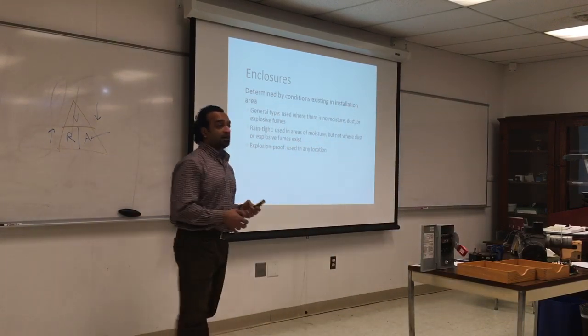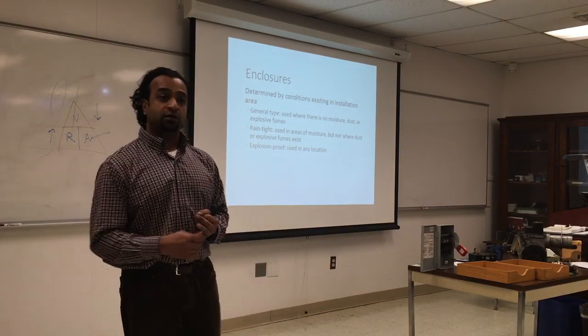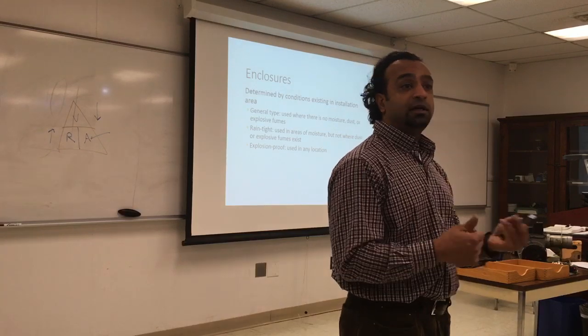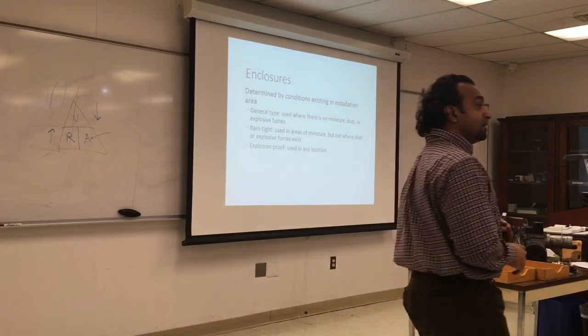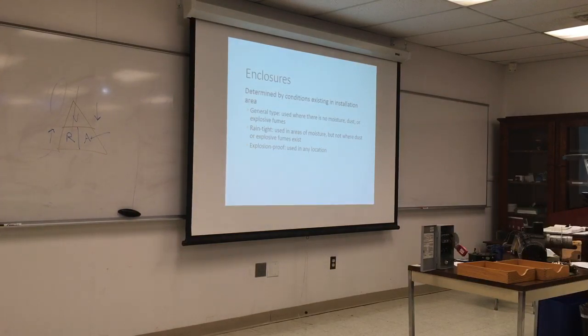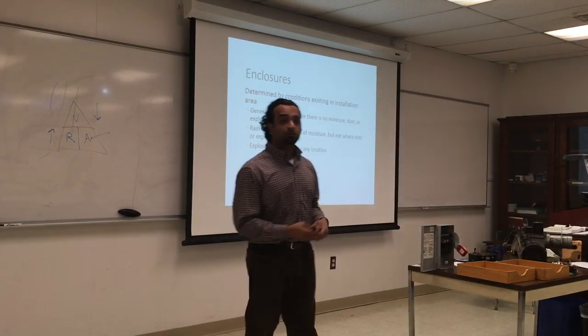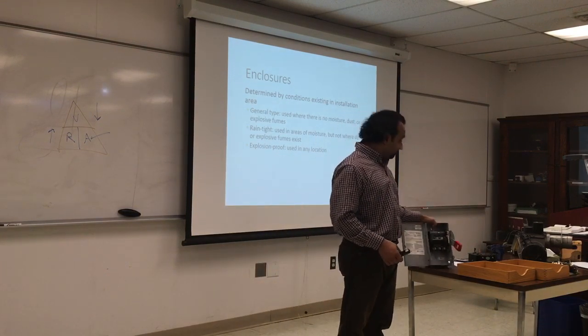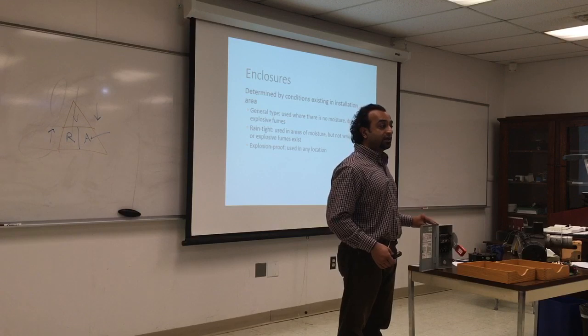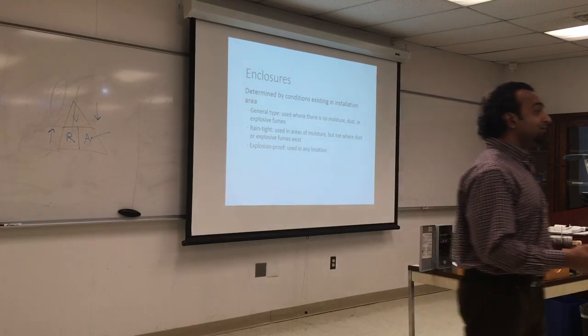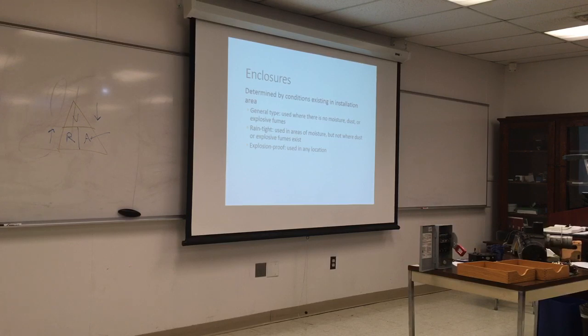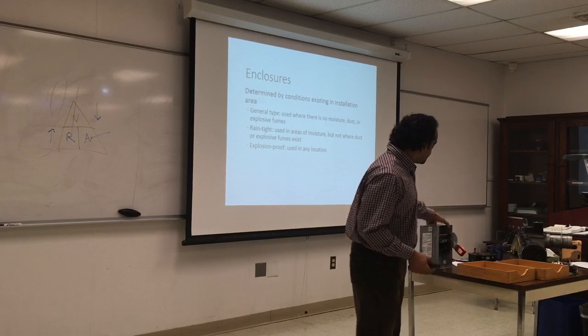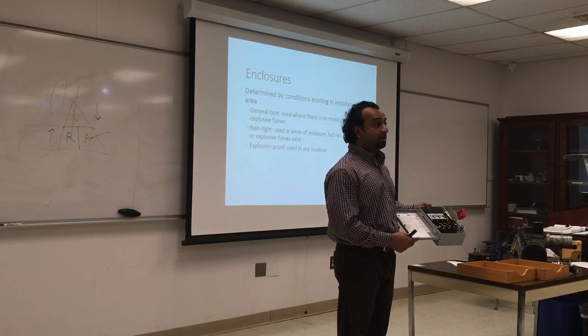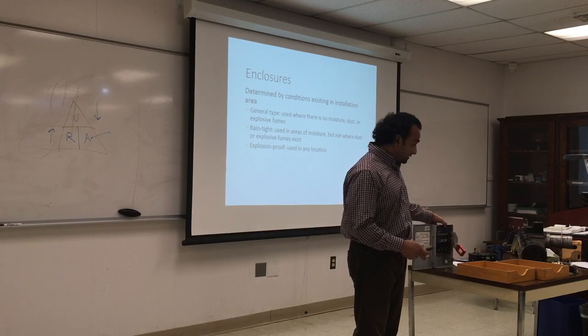Rain tight, these are for outside. So if you are going to put an enclosure for a compressor outside, you want to make sure it is rain tight, and also airtight sometimes. What happens when you place these outside, a lot of insects like to build nests in it, and they will be around the fuses. So make sure it's rain tight, so it does not oxidize or have a lot of moisture. Bees, wasps, and moths, they can get inside. They like the warmth. The wires are very warm, so they'll go inside. So that's something you want to check. If it's outside, it has to be rain tight.